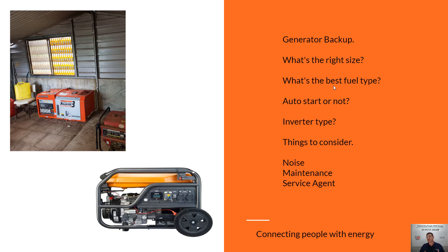If you do build a box, it's really important that you vent it and make sure the exhaust gases can get out, and that you can get clean air from the outside in so it doesn't suffocate itself. Auto starts — most generators these days come with a two-wire auto start. Make sure it's compatible with the solar system. That basically means if you're using a big load or your batteries are flat, the generator can automatically start and charge your batteries up without you having to think about it. If it hasn't got an auto start, you're just going to need to go outside and turn the generator on manually.